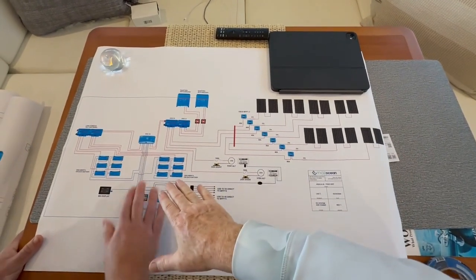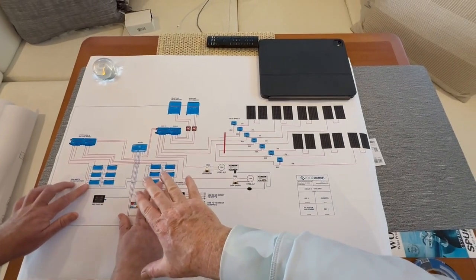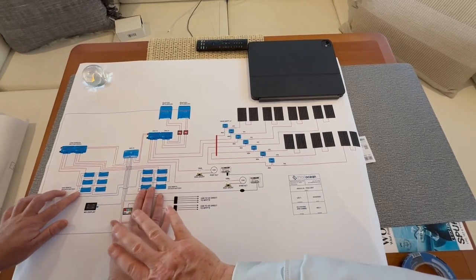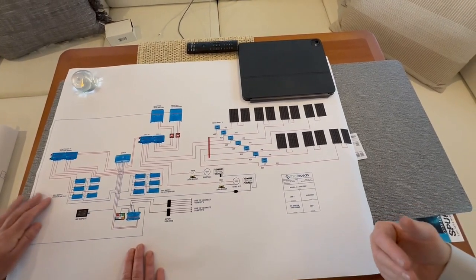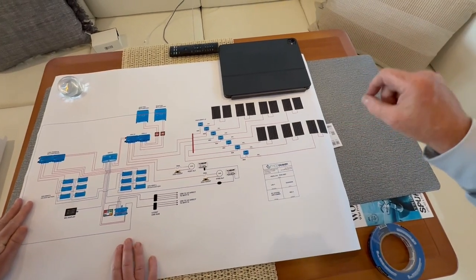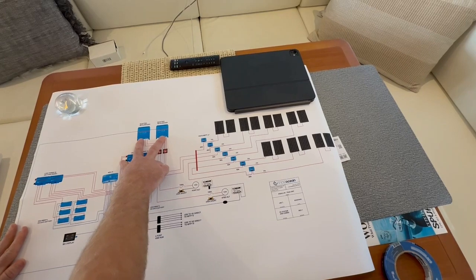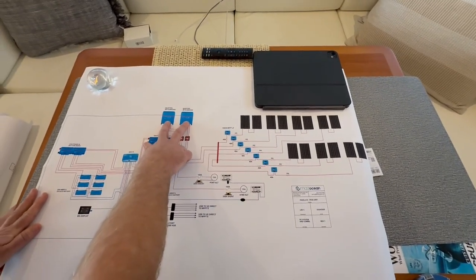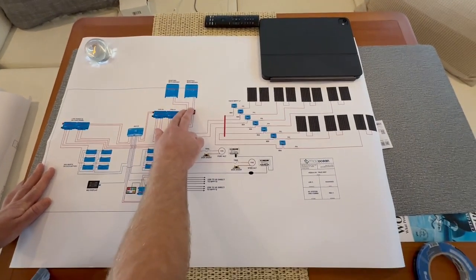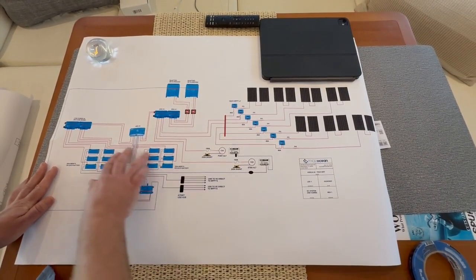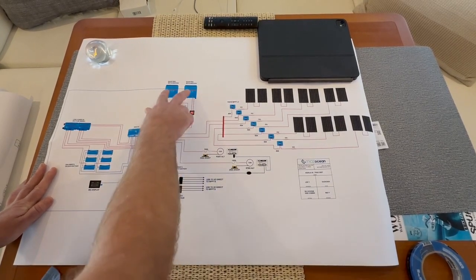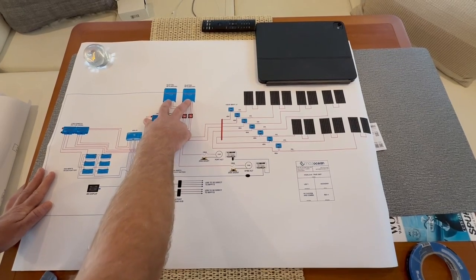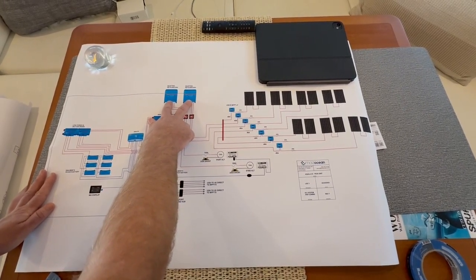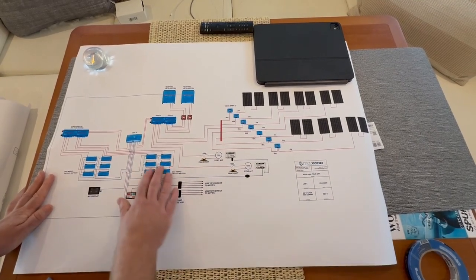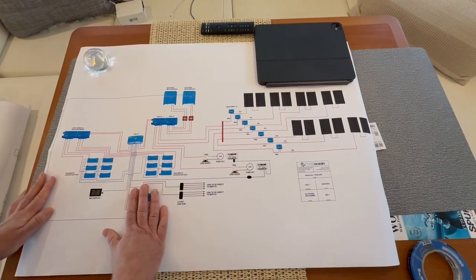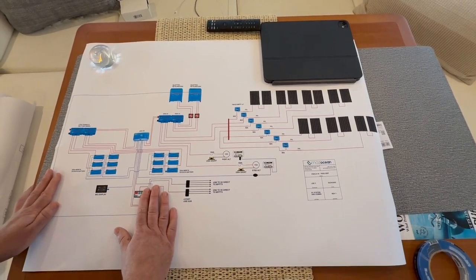So the battery bank is really the storage for the electrical system to consume from. How do we get the power? We talked about our 2 Quattros earlier - those are your big chargers as well, both inverters and chargers. When we have generator or shore power, the Quattros are putting in a huge amount of charge to charge the batteries. That's one reason we went with 2 of these - it reduces generator runtime significantly, because they can push a huge amount of charge into the batteries very quickly. We have that at about 10 kW, 50 amps, 10,000 watts of input.